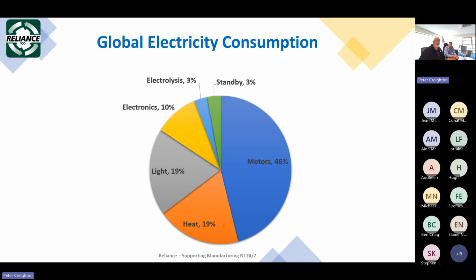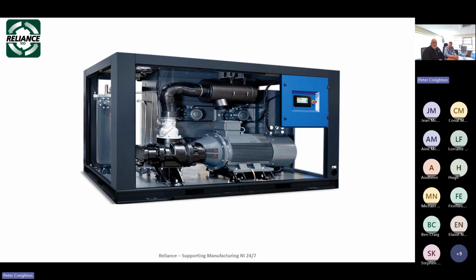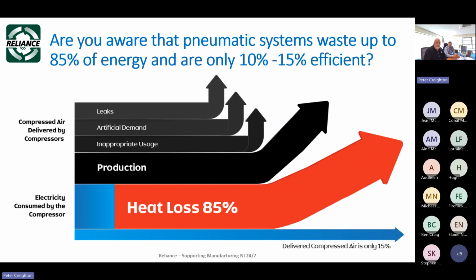And anything that I can offer anybody to help reduce their carbon emissions and to help reduce their electricity consumption is well met. So I'm going to go through the two biggest users of electricity in manufacturing. The first one would be a compressor. So anybody who has pneumatic air in situ knows that the motor in their compressor is by far the largest single standing motor that they would have in the facility, which is grand when you have a 200 kilowatt motor. And you find that a 200 kilowatt motor is 85% inefficient.